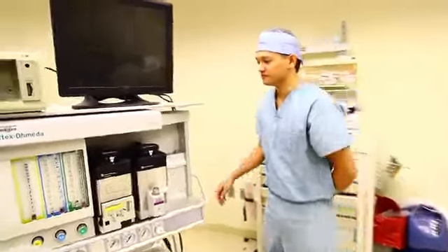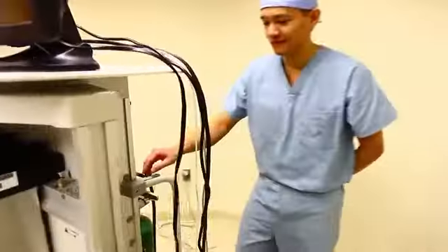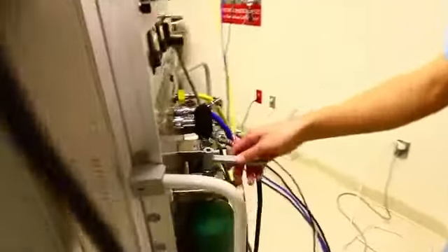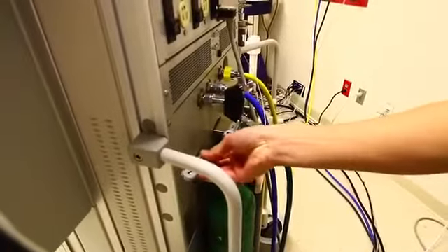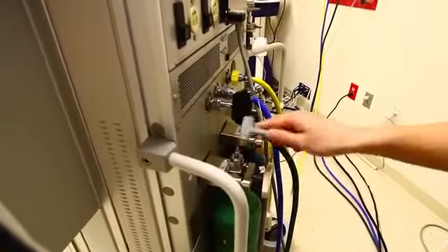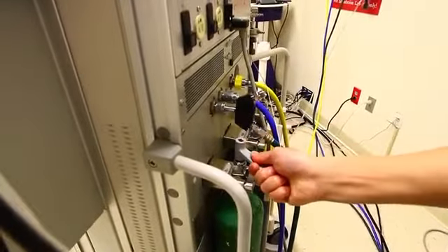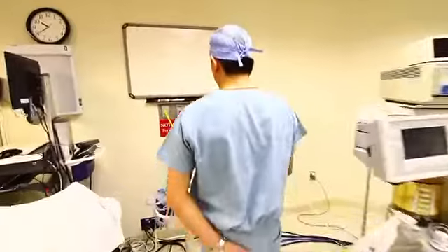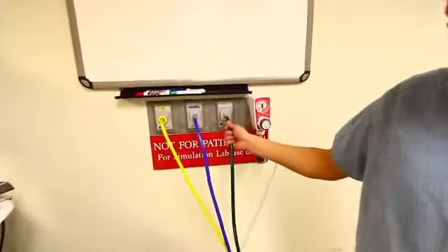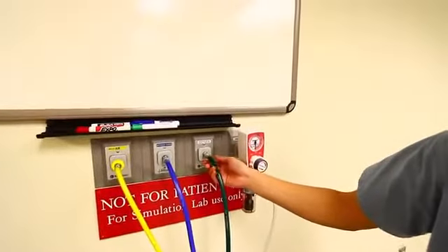The next thing you want to do is to ensure that the oxygen cylinder is closed. So just go in the reverse fashion, in a clockwise fashion this time, until it's fully closed. The next thing you want to check in the high pressure system is that your lines are connected to the wall outlets.